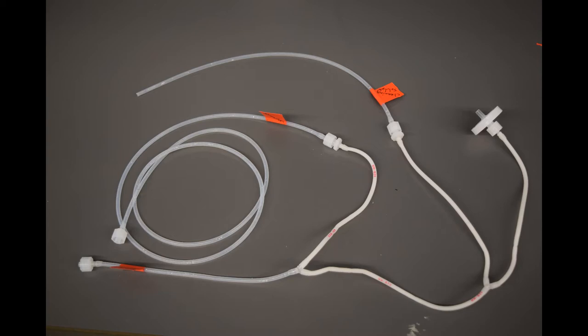The left branch of the second Y has a female luer lock barb which connects to another male luer lock barb with a section of tubing that extends to the cleaning solution. This section of tubing is approximately 30 centimeters long. The right branch of the second Y has another male luer lock barb with a 0.2 micron sterile filter connected.